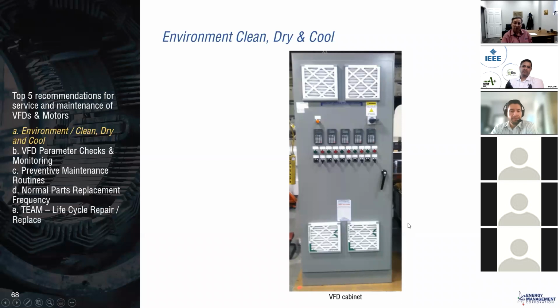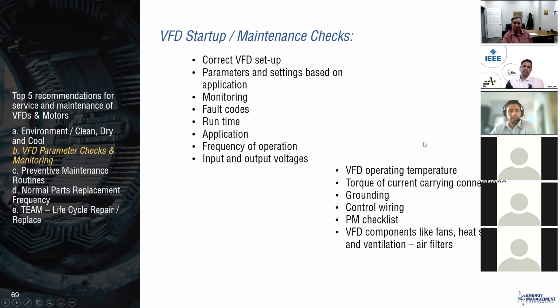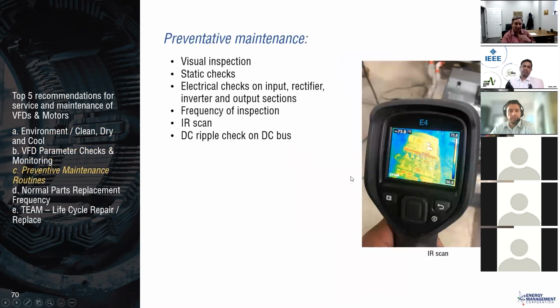We like to try to find a way where we can have our filters removable without opening the cabinet. That's not always possible, but that's a great way to do it. Also, being able to monitor the fault codes and those kinds of things is an important thing, we think, in this second area of parameter checks. When we do preventive maintenance, you'd be surprised how often we find a loose connection. Some of them are actually on the manufacturer side of a reactor, a load reactor, or something like that.